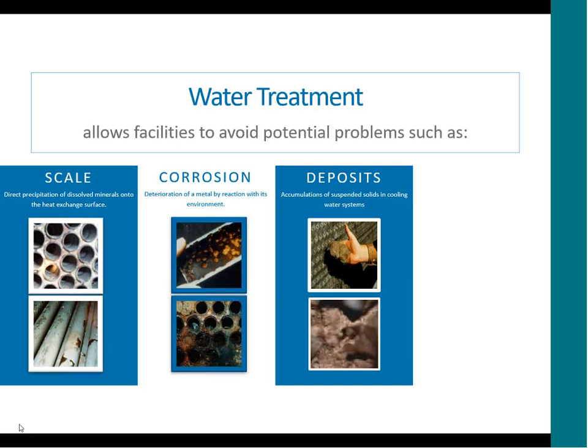Deposits. Deposits are the accumulation of suspended solids in the cooling tower system. The tower system is open to the atmosphere. It works as a great air scrubber, air filter. So anything that's in the air can end up in the cooling tower system. This time of year in the spring, we get a lot of pollen in the air, so we can have a lot of pollen end up in the cooling tower system. In the fall, when the leaves are changing and falling, you can end up with a lot of leaves in the system. Certain times of the year when we have cicadas, we could have a big problem. Cicadas end up in the cooling tower system. So deposits can be an issue in the water systems.